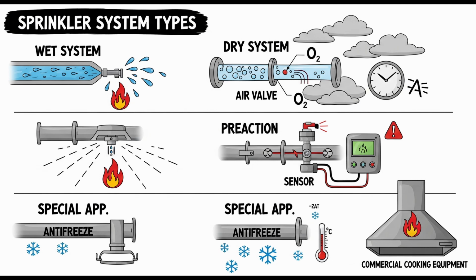The detection system supervision ensures that detectors and wiring are operational. This combined supervision provides a warning of system impairment before a fire occurs. Makes sense. Provides confidence the system is ready. Precisely. For single interlock systems, the air pressure, if used, is set per the manufacturer's instructions, and that air supply relief valve required for dry pipes can sometimes be omitted, if the air source used for supervision can't develop pressure above 15 psi.